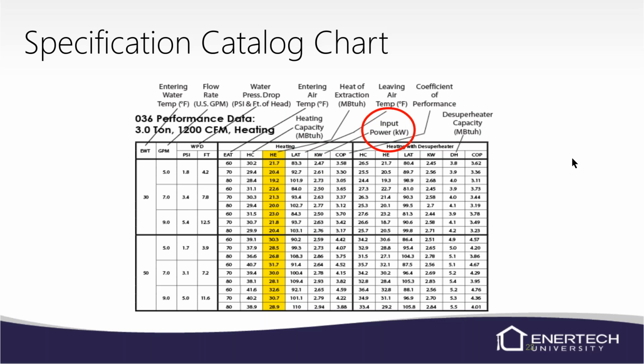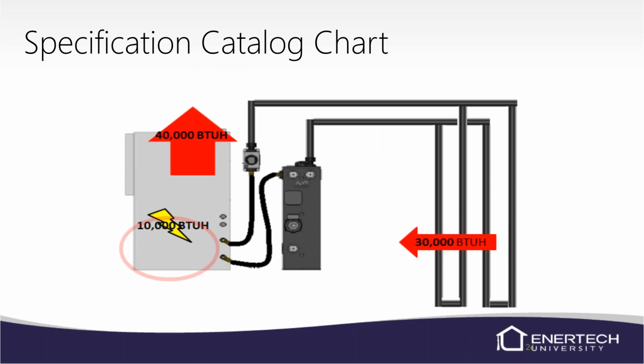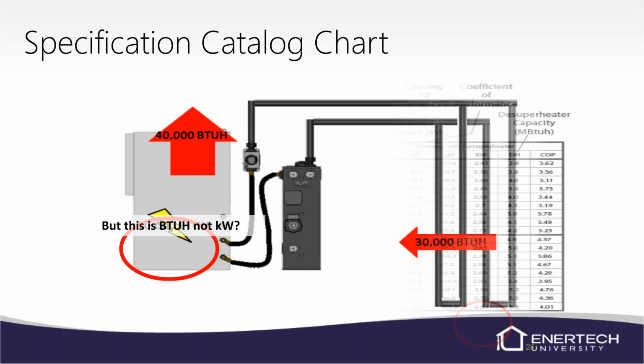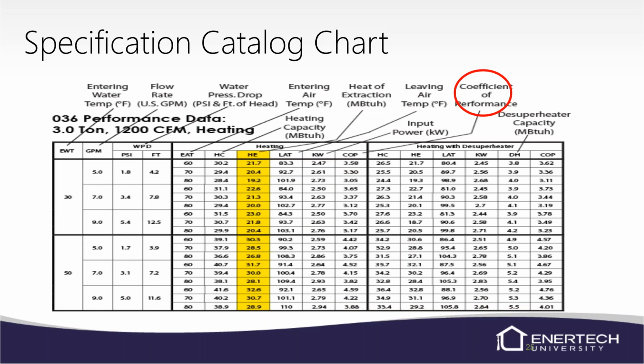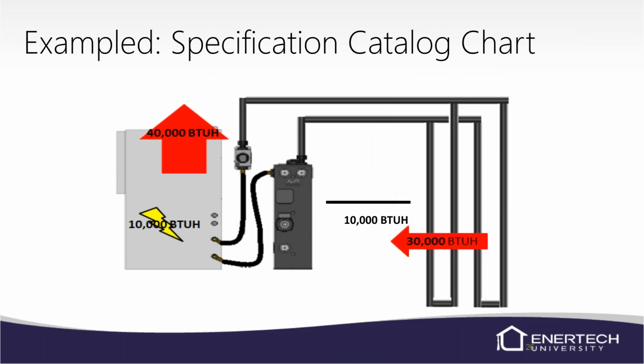Input, that's your power input in kilowatts. And that's your BTUs. That's your heat of compression. So once we get our kW, then we can multiply that times, I just forgot what that actually is. They'll probably show it here in just a second. But that's our power factor, basically, of the amount of kilowatts, and that's how we figure out our COP, coefficient of performance. Basically, coefficient of performance is how efficient the unit is.